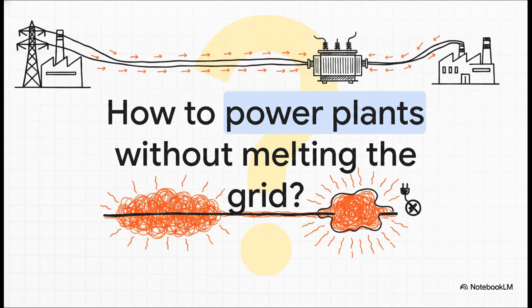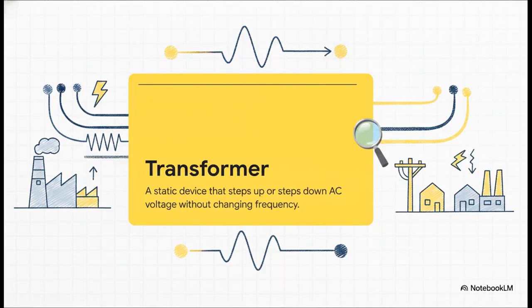Simple physics, guys. High current equals huge losses, specifically I²R losses. If we tried transmitting at low voltage, all that precious energy would literally just turn into wasted heat way before it even arrived at your facility. To solve this massive problem, we generate electricity at, say, 11 to 25 kilovolts and then step it way up to 132 kilovolts or higher for efficient long-distance transmission.